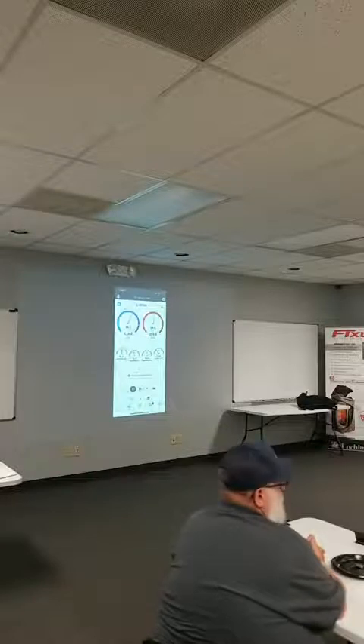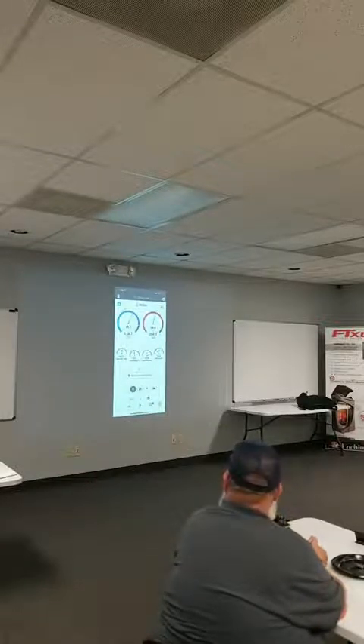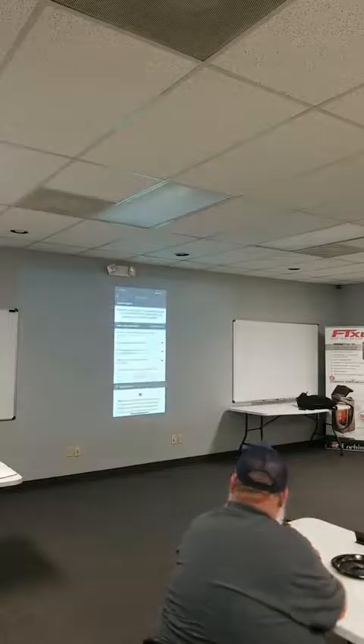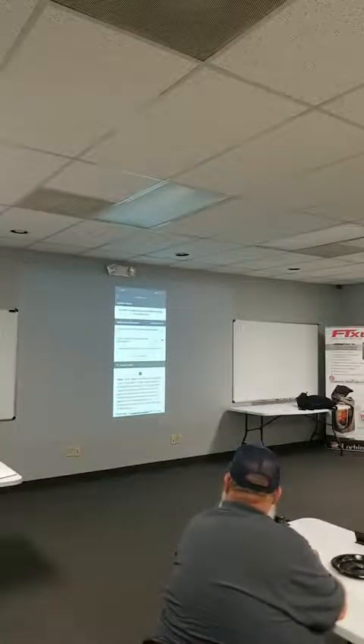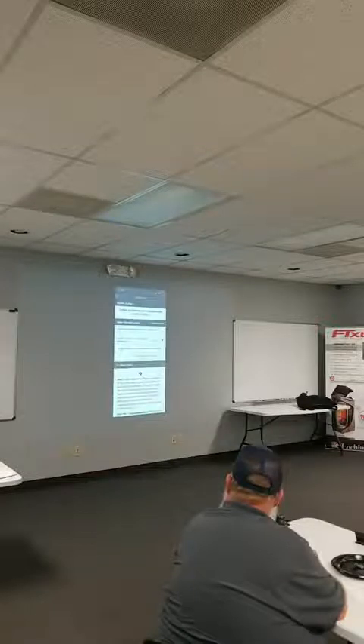There's no duct system on there, so that's sort of a notification and it's not stable. Let me clear this for a minute and move the outdoor sensor. So with the liquid line below the outdoor air, what else could cause that?